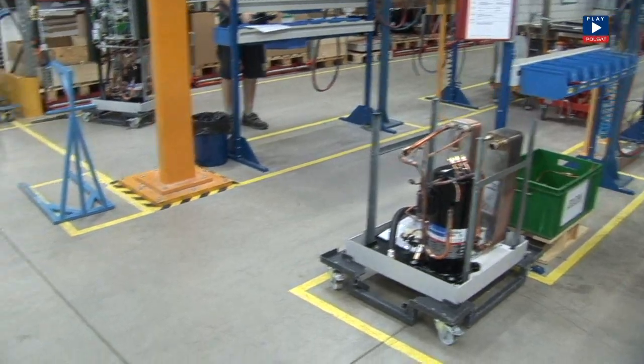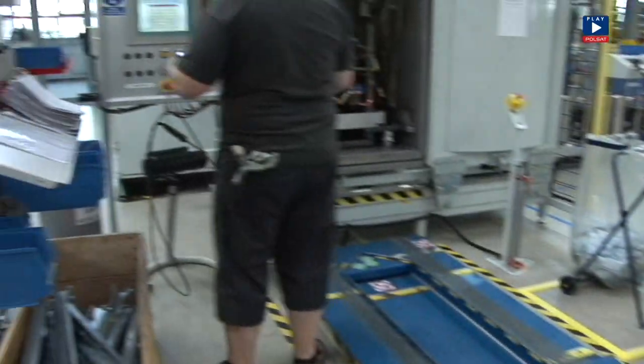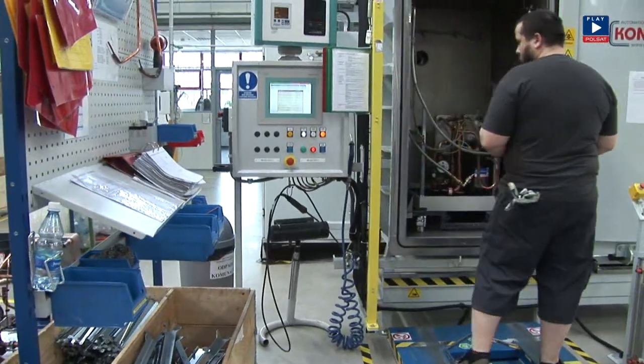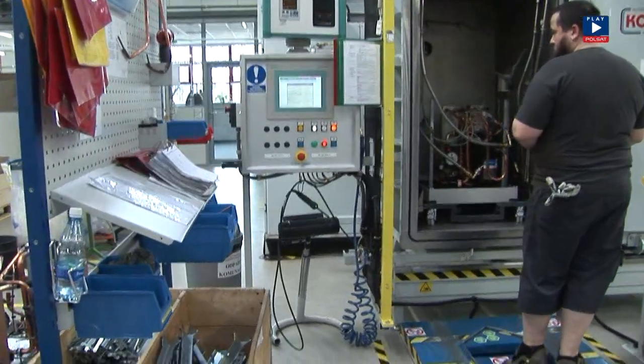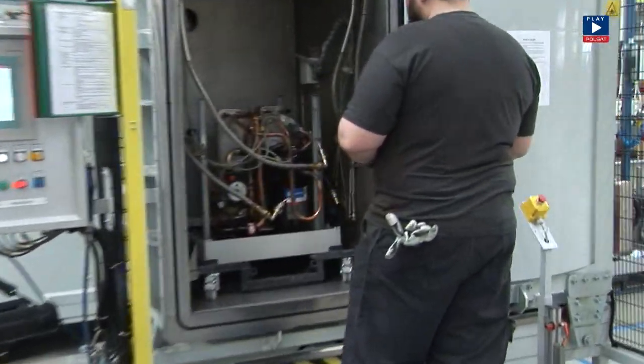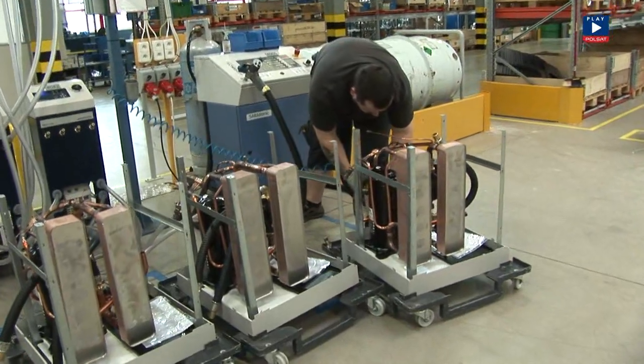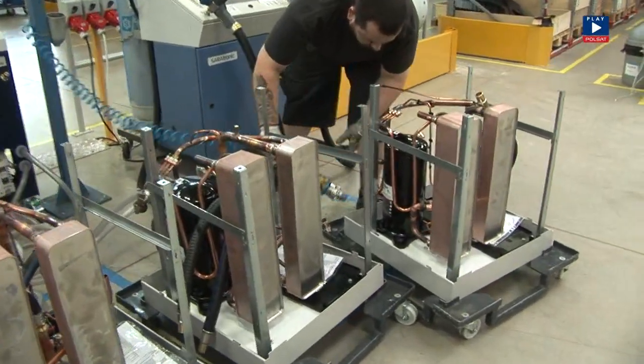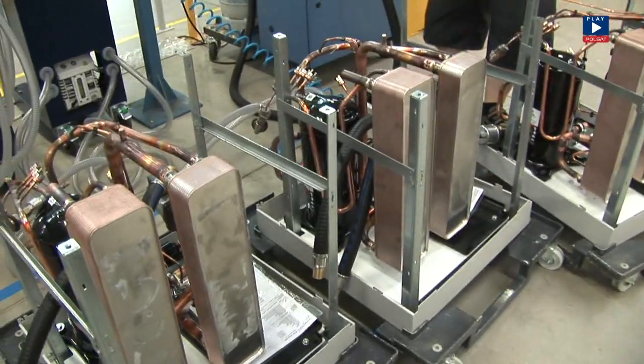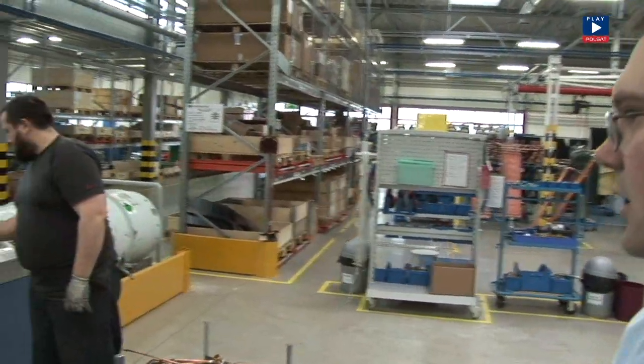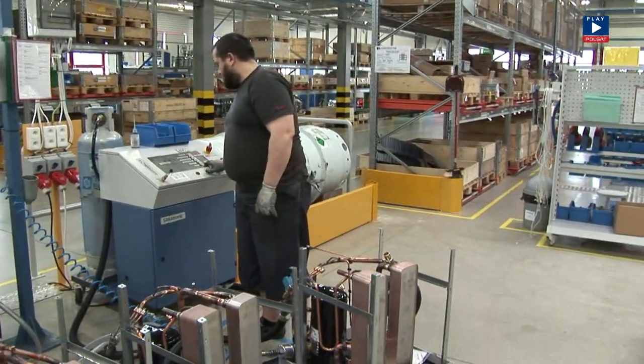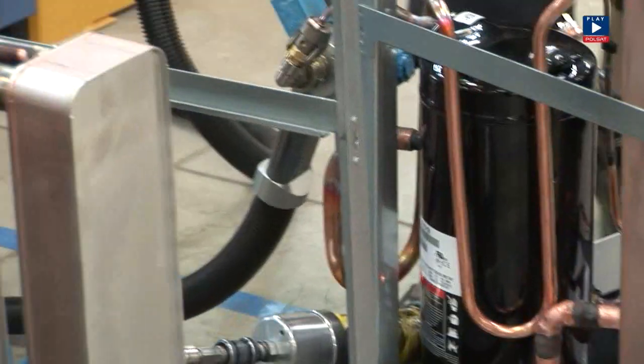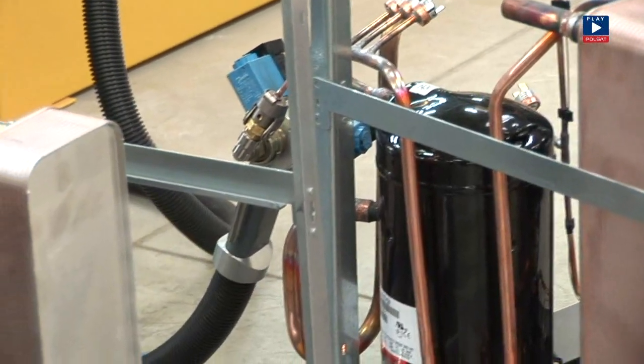The next very important process which guarantees the quality of the heat pump is the leak test. After the inspection, when the test has been passed, we dry, remove humidity and create a vacuum in a future refrigerant circuit. You can see the operator fill the system with an appropriate type of refrigerant. The refrigerant is to be hermetically sealed so that it cannot escape to the atmosphere.